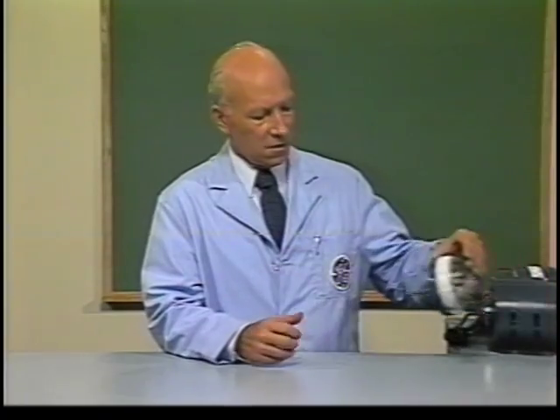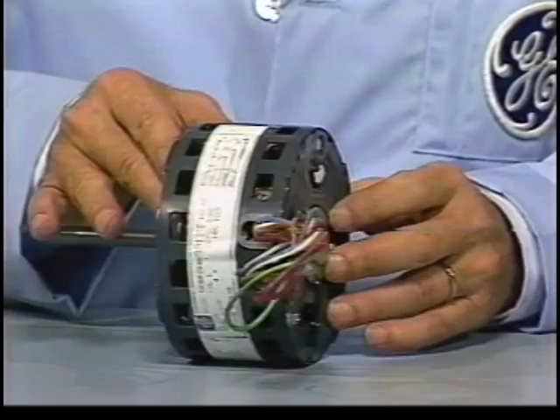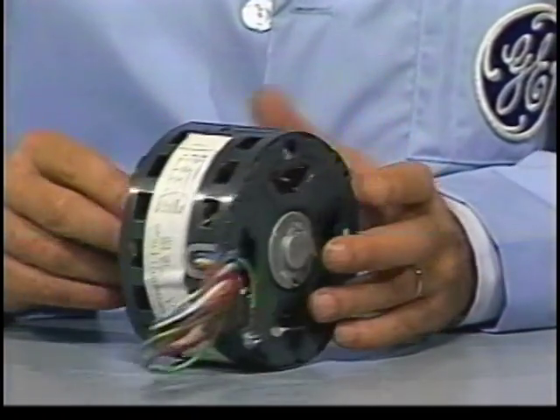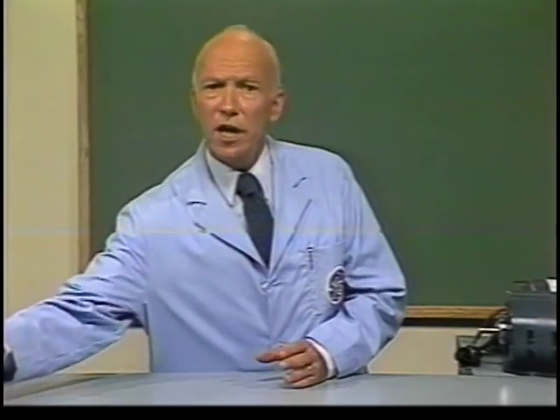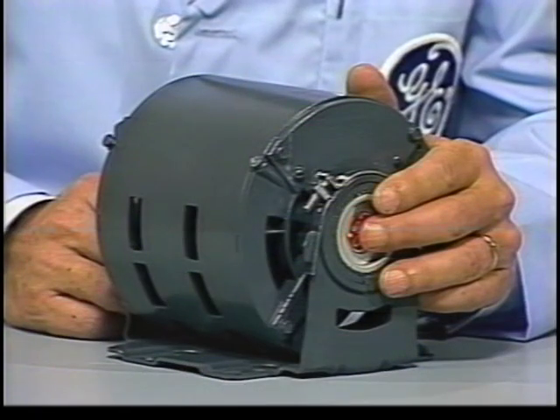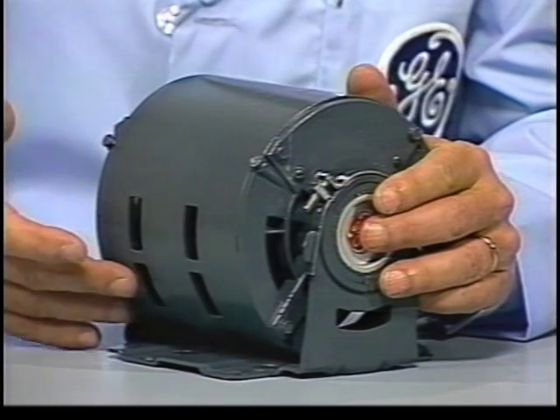In our last program we introduced the various mechanical features of FHP motors, including enclosures, bearings, and motor mountings. There are four types of motor enclosures. The first is the open enclosure, which has a number of ventilating openings allowing external air to enter and cool the motor windings. A variation is the open drip proof enclosure, where the ventilating openings are found only in the bottom half of the motor, allowing air to enter but not drops of moisture.